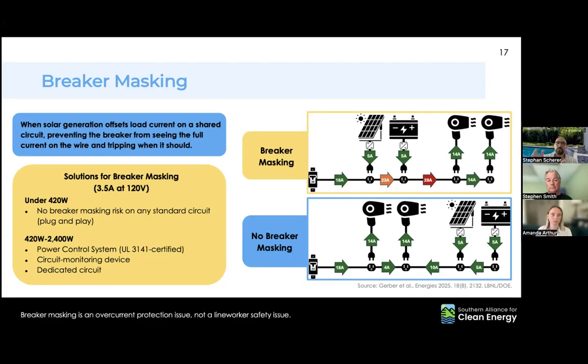So for that use case, the NEC gave us an out. It said you can still put plug-in solar on that system, you just have to make sure that the total power on that circuit, including the solar power, doesn't exceed 1800 watts on a 15 amp breaker, for instance, or 2400 watts on a 20 amp breaker. There are different stages depending on wire thickness, essentially.